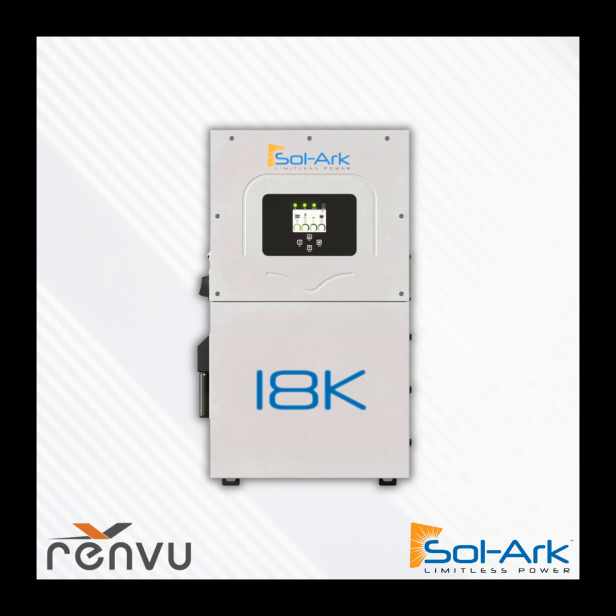I'd also say this is with 48 volt architecture, and as far as installers who like to set it and forget it, you're going to have less problems with 48 volt batteries than you would with higher voltage batteries, especially if there's an expectation that you might have to service the battery down the road, or that the customer might have some prying hands and start to monkey around with their system. 48-volt architecture is simply a safer architecture than high voltage, and more proven.